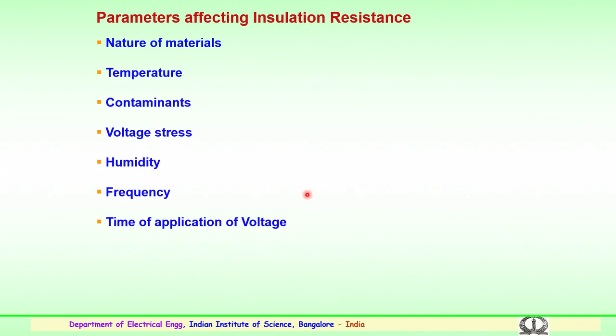So, the voltage stress, which is continuous stress applied over a period of time till the operation of the equipment which it is designed for, and the environmental factors like humidity, the change in humidity, could also affect the insulation resistance, the frequency of the equipment which is being operated, and the time of application of voltage. The time of application could again be equipment specific, where like a transformer it is continuously applied. So, where it is continuously stressed, electrical stress is continuous for years to years. So, these are the parameters which could affect the insulation resistance.